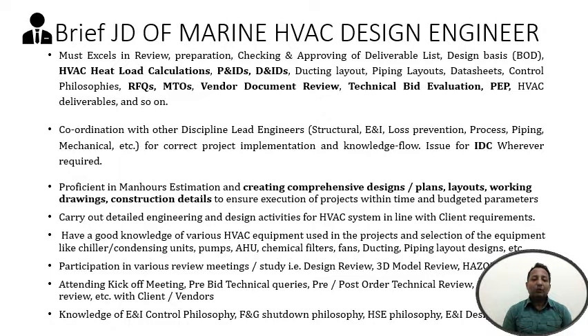Next is having good knowledge of the various HVAC equipment used in projects and selecting equipment like chillers, condenser units, pumps, AHUs, chemical filters, fans, ducting and piping layout design, etc. This means a person should have overall knowledge of various HVAC equipment used in the project, be able to select equipment based on project conditions, and be well versed with catalogs of various equipment manufacturers to pinpoint model selection based on the calculated heat load and subsequent project conditions. I'll touch on this point in subsequent sessions as well.